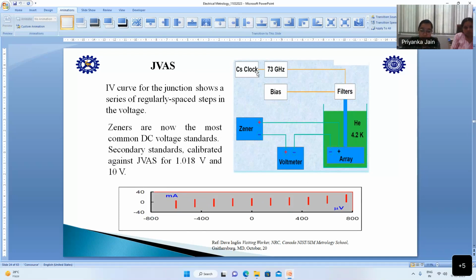So this frequency generator is calibrated against our frequency clock. In case I am generating 73 gigahertz of frequency from a generator and applying it to the Josephson array, this Josephson array is situated in a helium container, a liquid helium container. This is to avoid the temperature noise, that means to avoid any noise. So we keep our Josephson junction array inside this container.